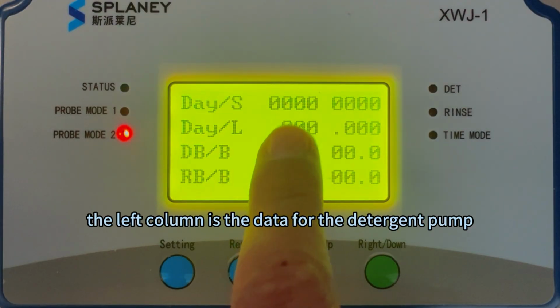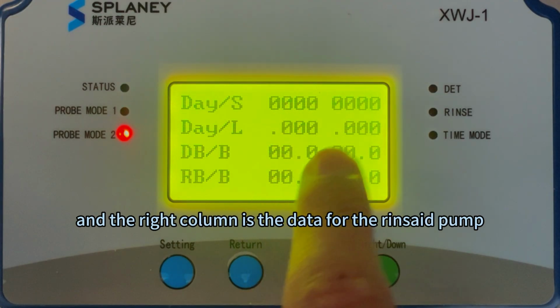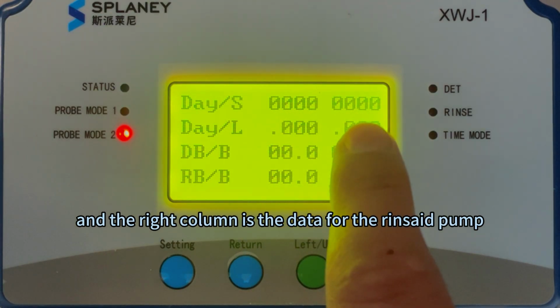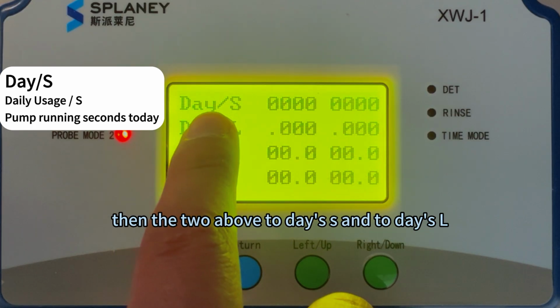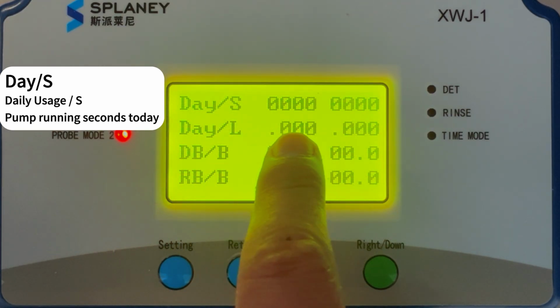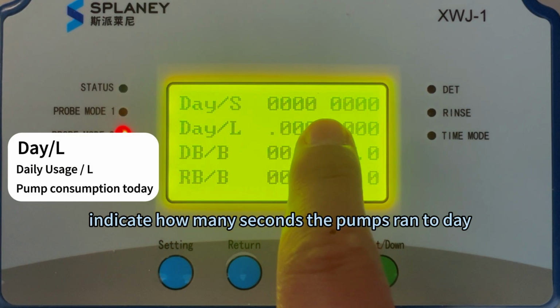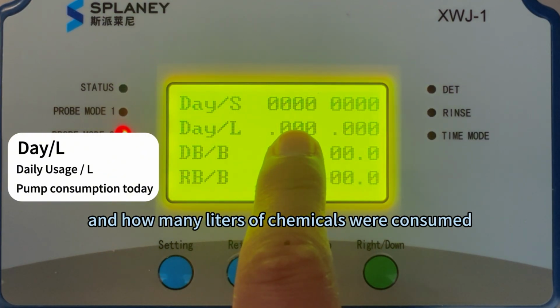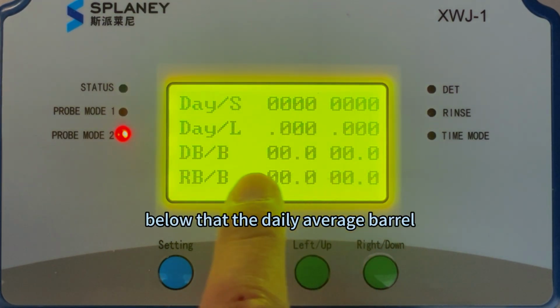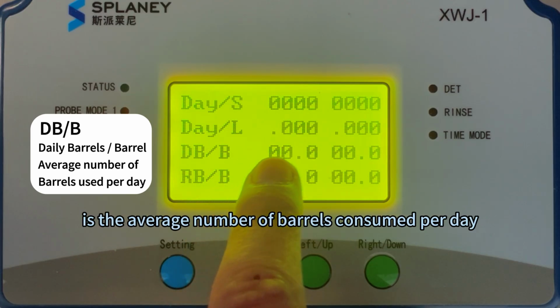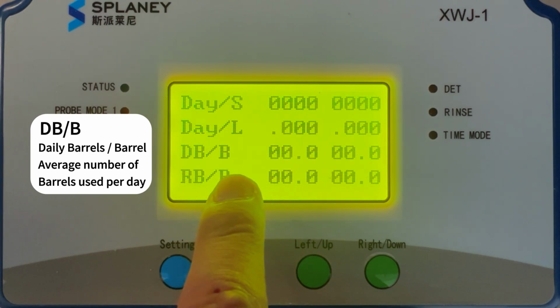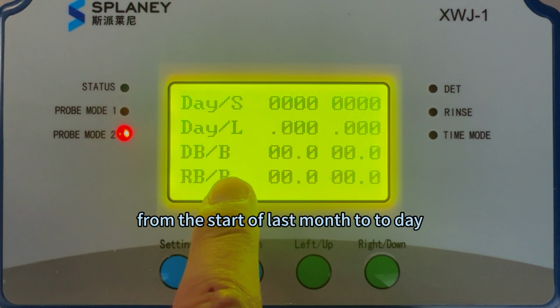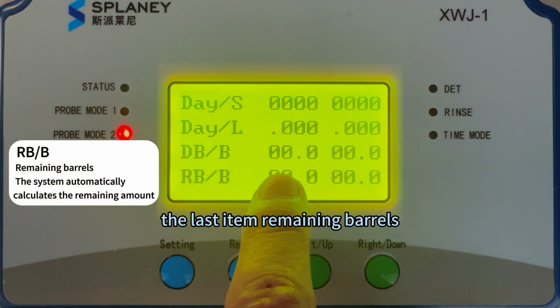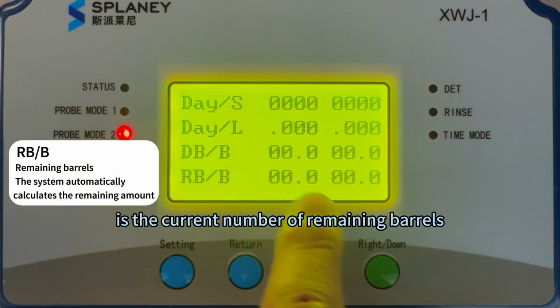First, the left column is the data for the detergent pump, and the right column is the data for the rinse aid pump. Then the two above, today's S and today's L, indicate how many seconds the pumps ran today and how many liters of chemicals were consumed. Below that, the daily average barrel is the average number of barrels consumed per day from the start of last month to today. The last item, remaining barrels, is the current number of remaining barrels.